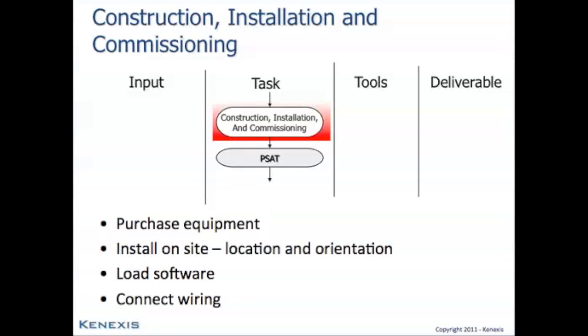After the installation, the software needs to be loaded onto the system. The wiring needs to be connected, and all of the loops need to be commissioned to ensure that the instruments are operational and correctly communicating with the FGS logic solver.